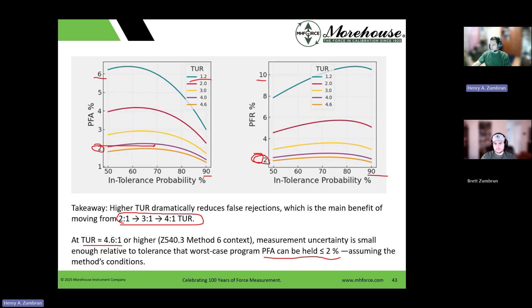Another question: what if the tolerance were plus or minus 5 in the CMC? So what do you think happens here? This is the TUR of 1 to 1. What did we learn? We learned that for the 1 to 1, there's going to be a higher probability of false accept. So there's a good chance the calibration provider adjusted something that may have actually been good.